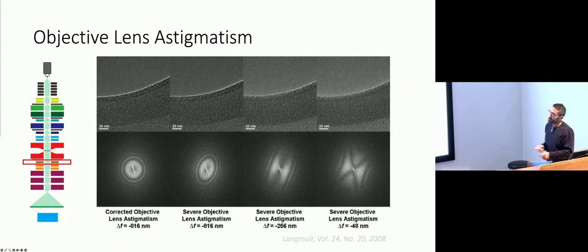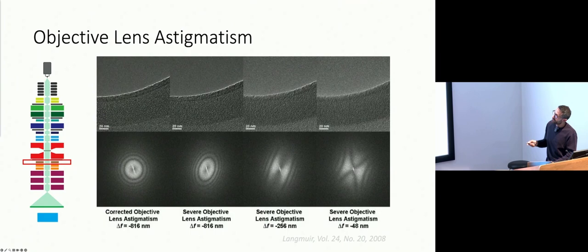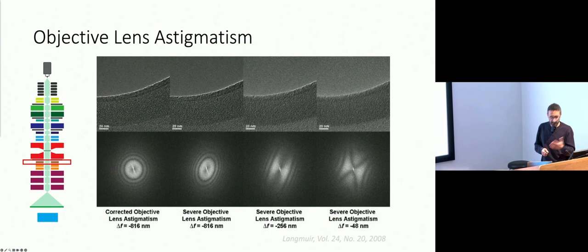Another alignment is objective lens astigmatism. Astigmatism means something that is not circular — lenses, although highly engineered, are still not perfectly circular. This is revealed by taking an image and looking at the power spectrum. If the power spectrum is circular, there is no objective lens astigmatism. If it looks oval, parallel, or hyperbolic, there is astigmatism — either slight or severe. Astigmatism can be fixed using automated routines in all data collection software; you literally just have to press a button.